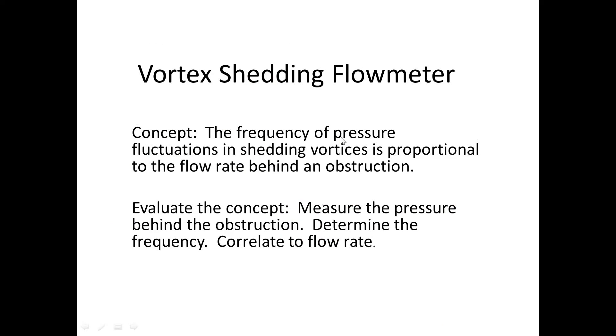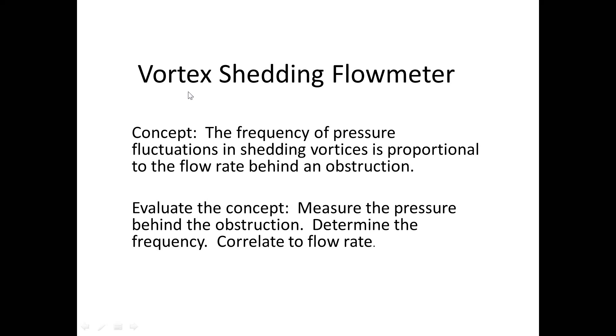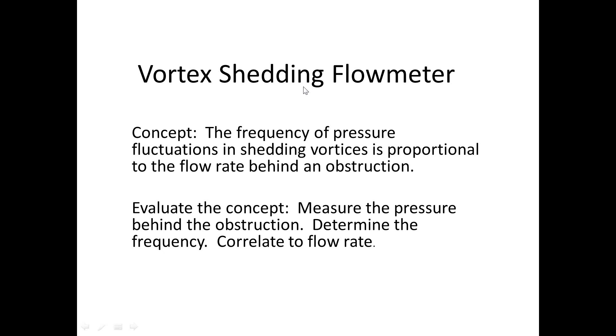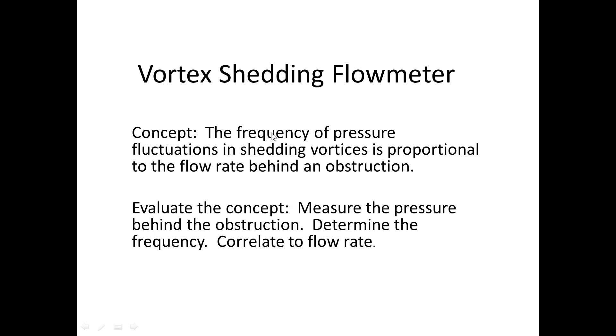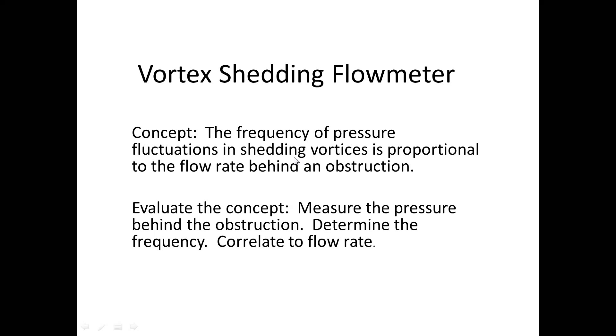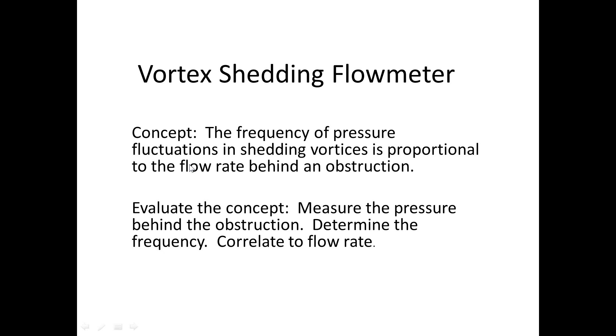What I want to do is take this interesting phenomenon and use it for a useful application. The application will be a device called the vortex shedding flow meter, something that you can go out and buy. It uses this process of shedding vortices to measure the flow rate in a pipe. As the vortices are shed alternating one side then the other, that causes a pressure fluctuation.